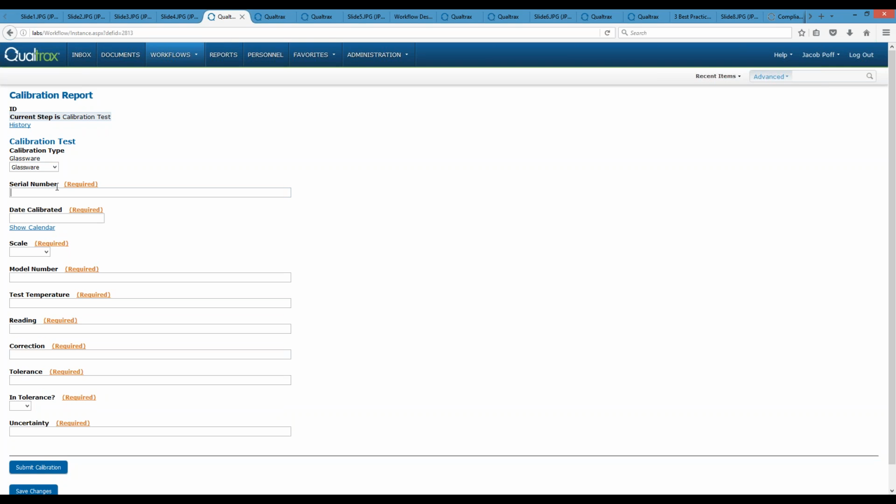And so when you pop back over to your name standards and your ISO 17025, if you're with your auditor and they want to know how you are managing your full control of monitoring and measuring devices, this is a great way to show them. We've got our document management that houses our document that explains the procedure. We have a way to test competency, and then on top of that, we have a way to make sure that the calibration report that they submit is accurate, just because we've got these workflows in place.